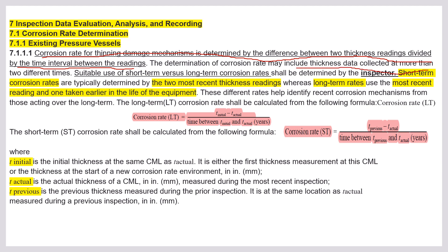We need to read the area from where we have to take the CML — Condition Monitoring Location — where we will take the readings and determine how many readings are required. If we collect readings at the correct frequency, only then can we evaluate the corrosion rate properly. To get a correct corrosion rate and remaining life, you need to take the data properly.